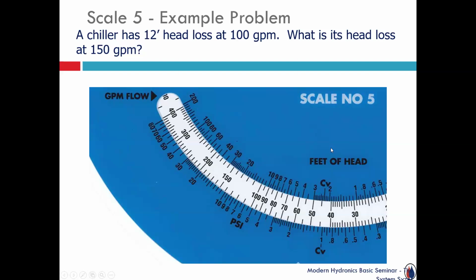Without moving that scale, now just go find the new flow rate. So in this case, 150 GPM, and read straight up. And that becomes your new pressure drop, about 27 feet of head. So 100 GPM, 12 feet of head, bump it up to 150. With that squared relationship, the pressure drop will now be about 27 feet of head. It's just a quick example of how, once there's one known flow and head calculation that's accurate, you can figure out any change in flow and what that change in pressure drop will be.